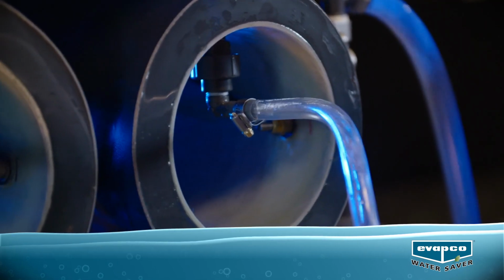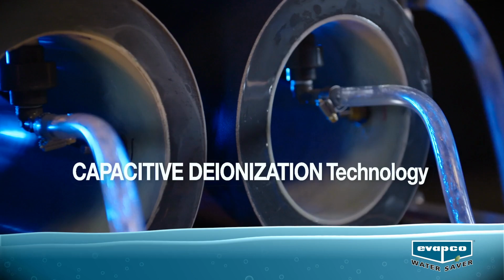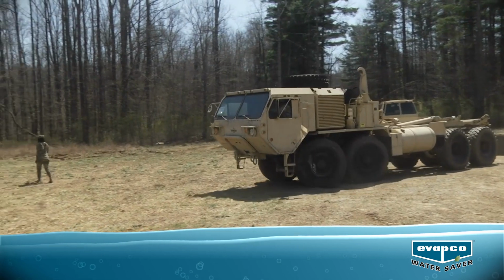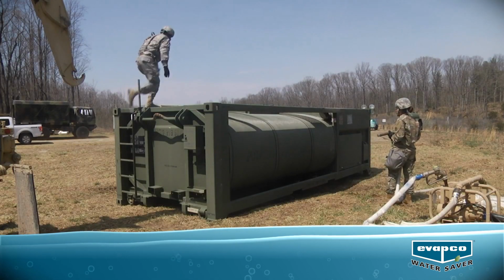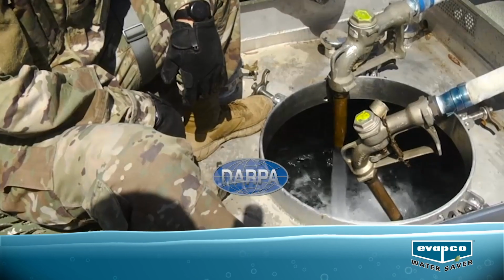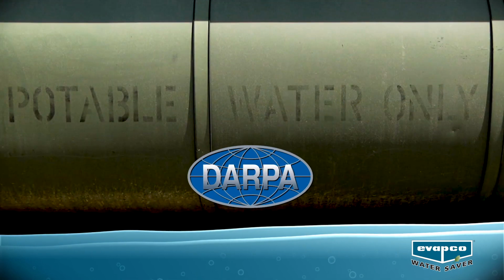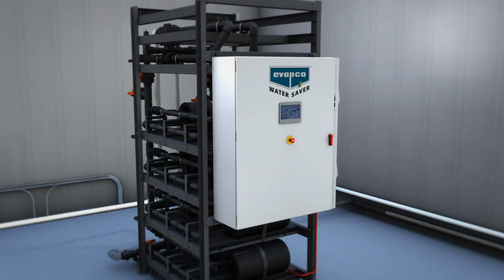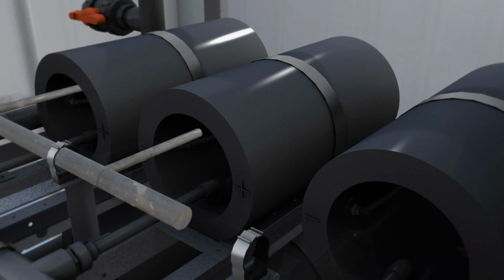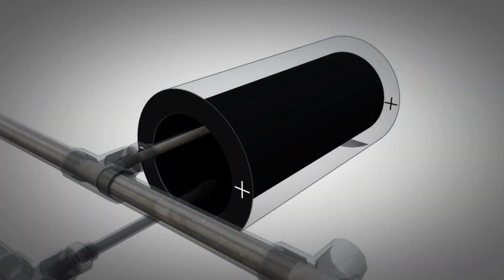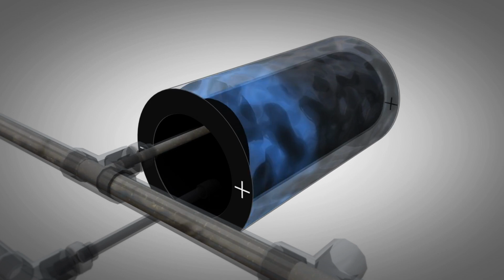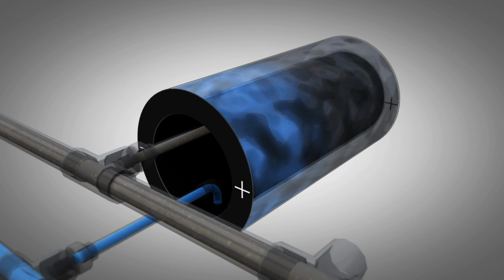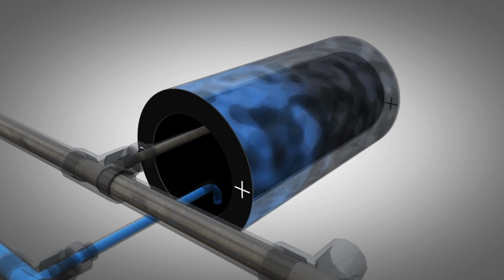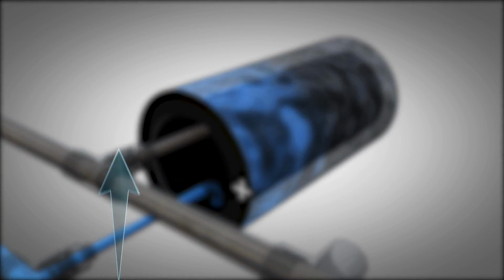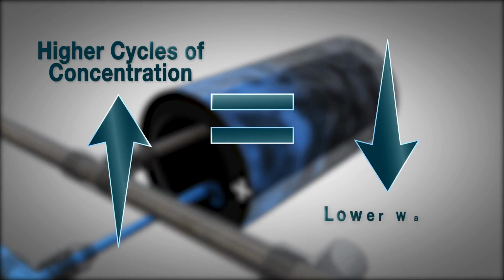The EVAPCO Water Saver utilizes capacitive deionization technology, which was originally developed under the United States Defense Advanced Research Projects Agency, commonly referred to as DARPA. As tower makeup water passes through the EVAPCO Water Saver, capacitors remove a portion of the dissolved ions, which lowers the conductivity of the makeup water.